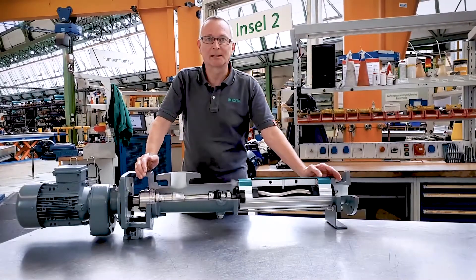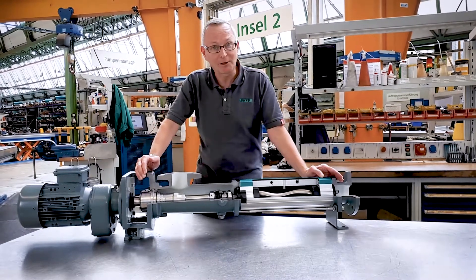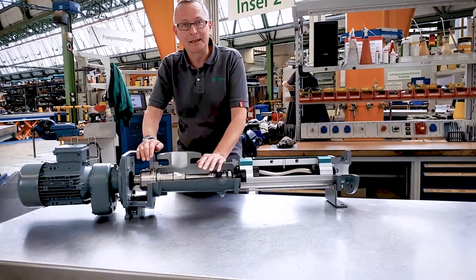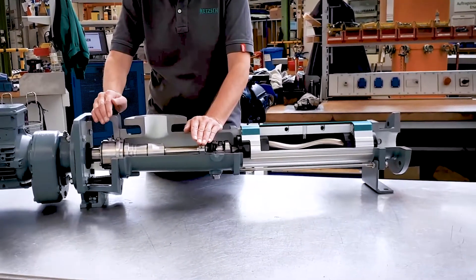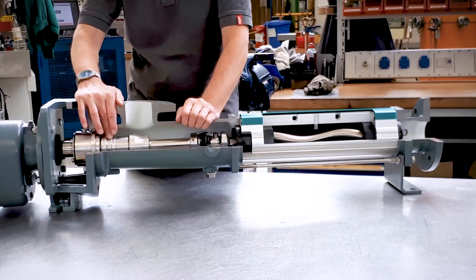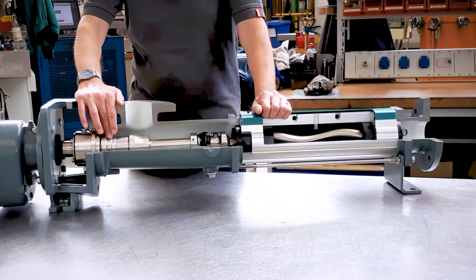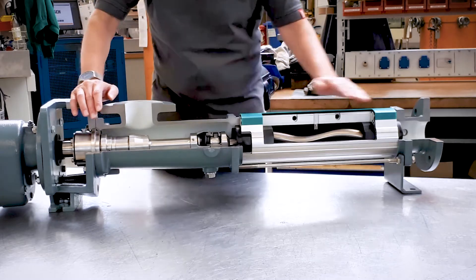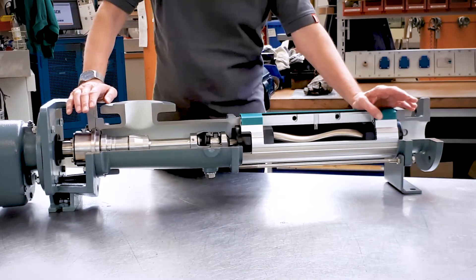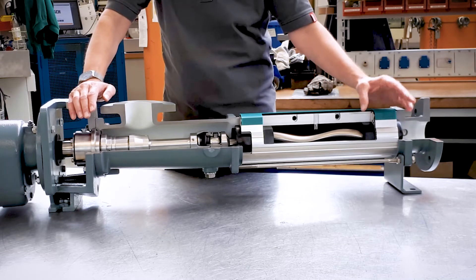What you see here is a standard configuration of a progressing cavity pump. The pump is bi-directional, but overwhelmingly this is the suction housing. The reason for that is that the mechanical seal only sees the suction pressure — that's a big advantage over many other pumping types. In terms of performance, we have four geometries which we use for different applications depending on viscosity or pressure.